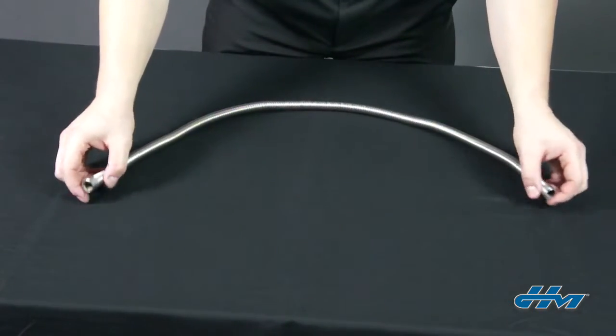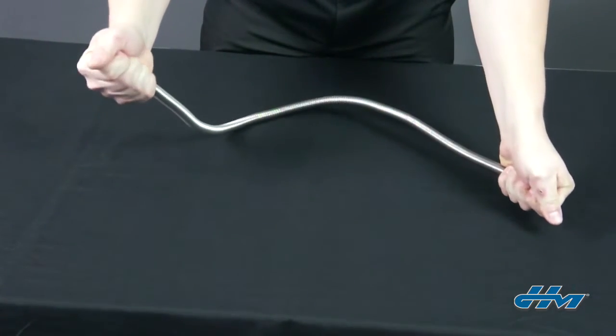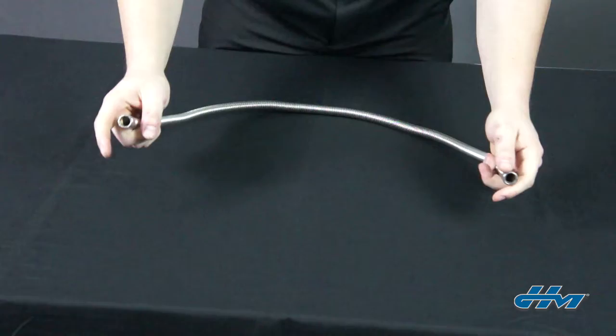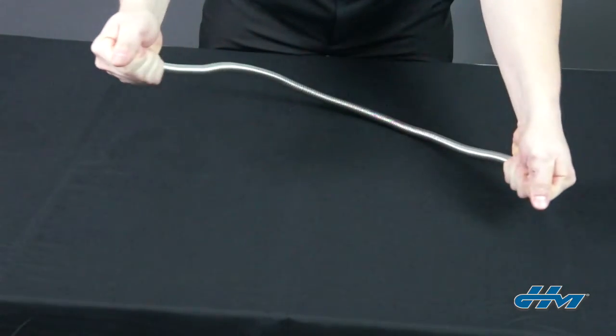Hoses can take a great deal of damage when they're torqued. Twisting it stresses the corrugations and the fitting welds and can cause it to fail. To prevent torque, don't install the hose off-center. When it tries to flex, the assembly will be torqued.